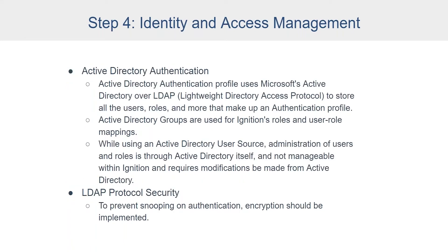Rather than just managing users in a database, what we often see are people using Active Directory authentication. The Active Directory authentication profile uses Microsoft's Active Directory over LDAP to store all users' roles and more to make up an authentication profile. Active Directory groups are used for Ignition's roles and user role mappings. When using an Active Directory user source, the administration of users and roles is through the Active Directory interface itself rather than managing them within Ignition. Multiple gateways can all connect to the same Active Directory, giving you one single source of truth.